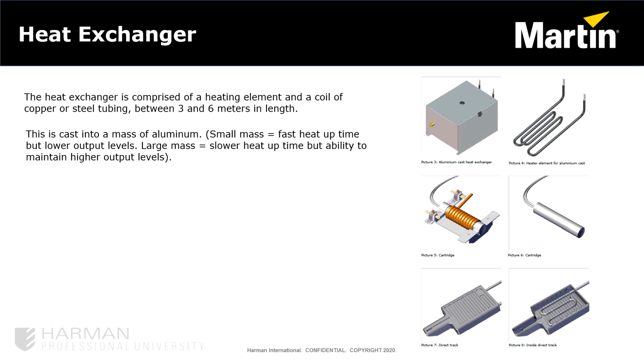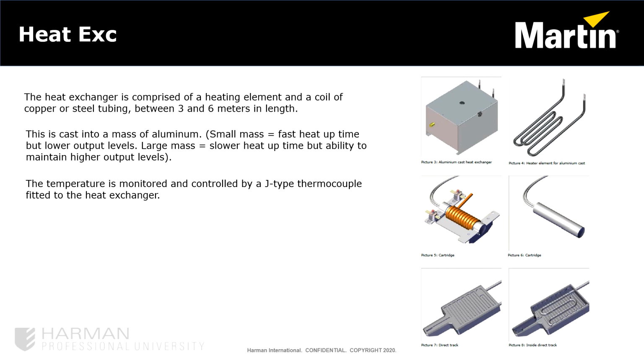The long length of the tubing is the reason why it is nearly impossible to clear an obstruction once the heater is blocked. A J-type thermocouple fitted to the heat exchanger monitors and controls the temperature. These are physically staked inside the aluminum block. The blocks are created and cast in 2 large ovens at the factory where the quality can be controlled.